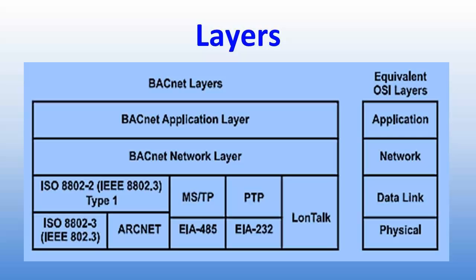BACnet has a layered protocol architecture based on a collapsed version of the Open Systems Interconnection OSI model. Layers 1, 2, 3, and 7 of the OSI model are used. Common application layer and network layer protocols are used with any of four options for local area networking. Technologies include point-to-point protocol suitable for dial-up telephone communications. The network layer provides a way to interconnect dissimilar LANs to form an internetwork.